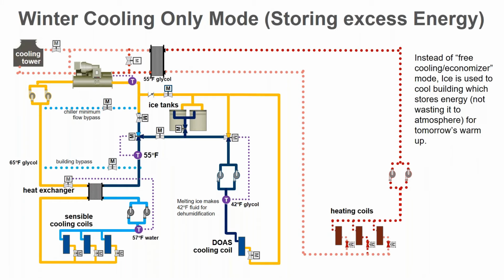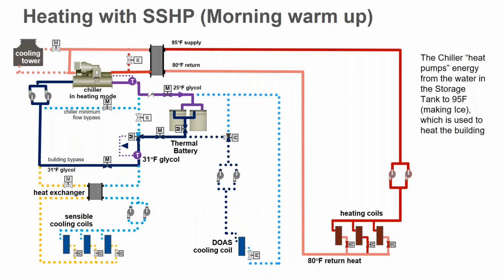And then finally, winter cooling mode. The tanks can be used for doing the DOAS coil or the sensible coils inside. In the winter time, there's not as much cold coil needed. The air is drier in the winter time, but certainly it can be done in particular situations that you may need. And then finally, heating, pretty straightforward with the storage source heat pump.